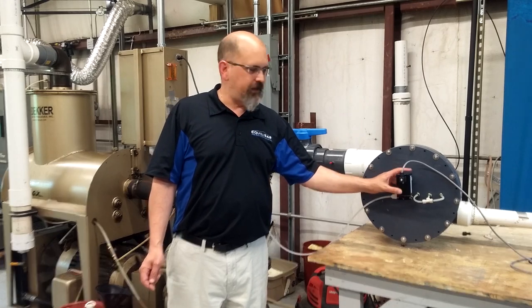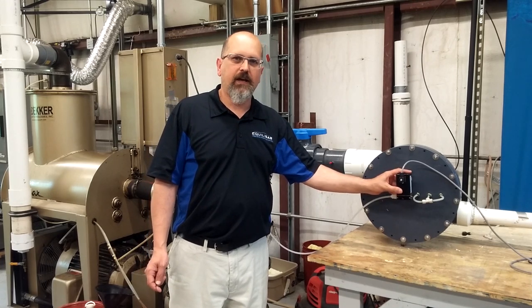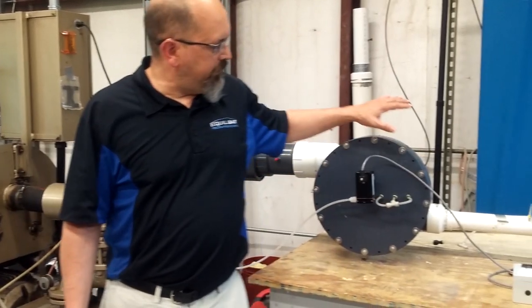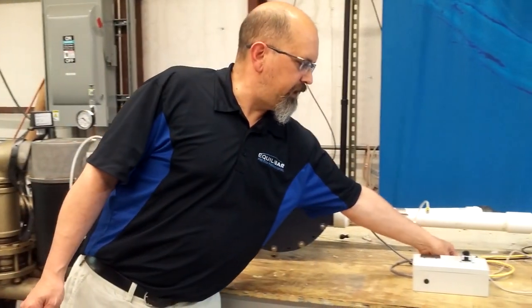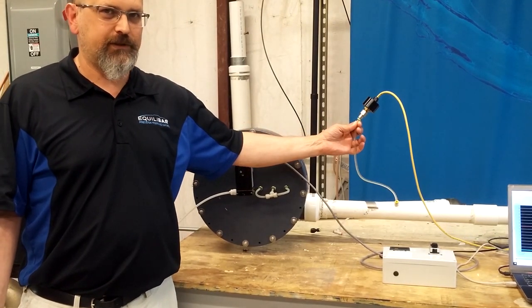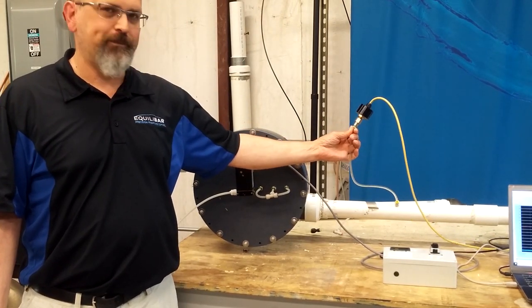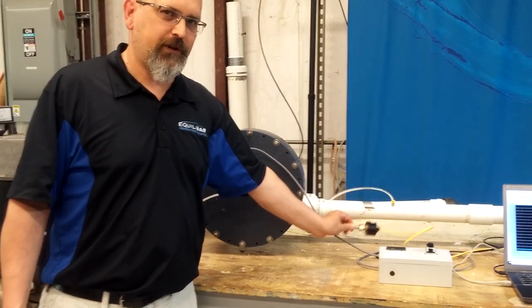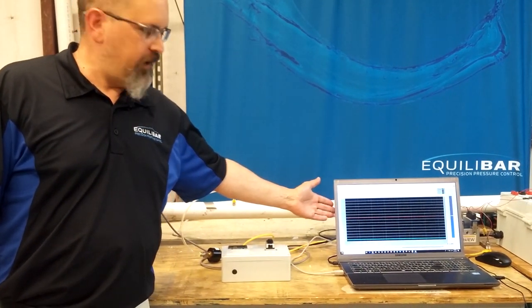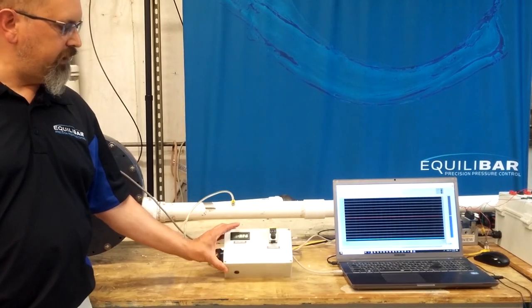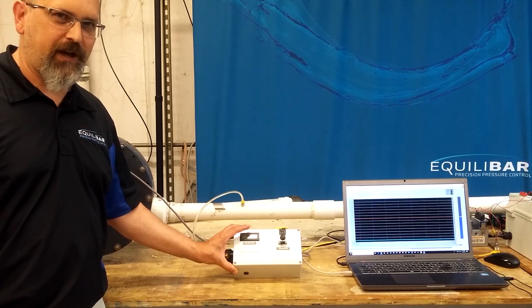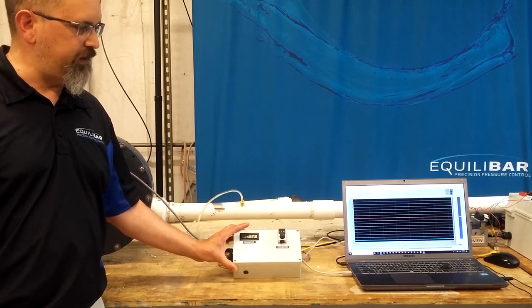Pilot operating that regulator is a QPV electronic vacuum regulator. The vacuum regulator is controlling the vacuum here, and we can see what that vacuum level is with this vacuum transducer. The vacuum transducer is going to display on this chart recorder. We're going to use this to establish the set point for the electronic vacuum regulator that's pilot operating the main vacuum regulator.